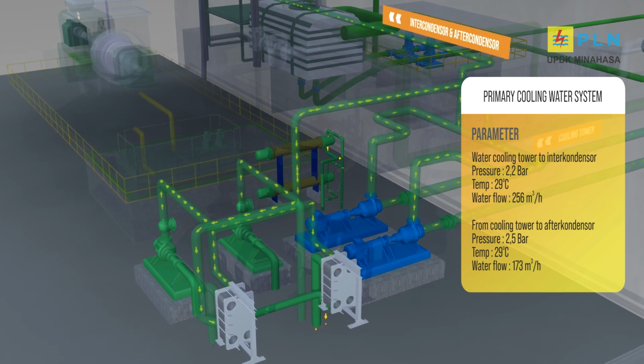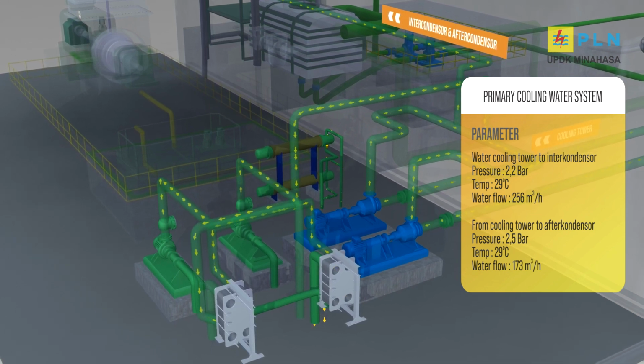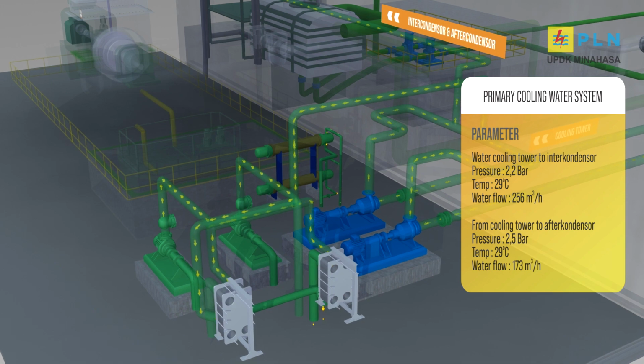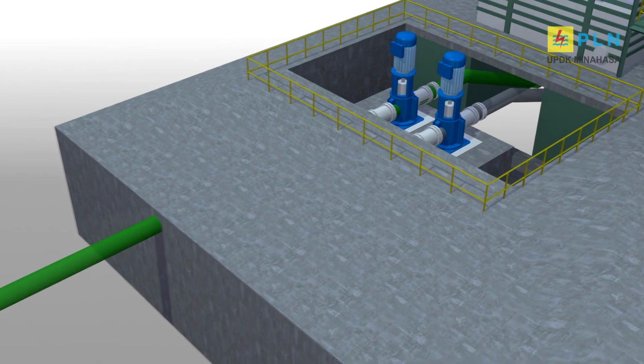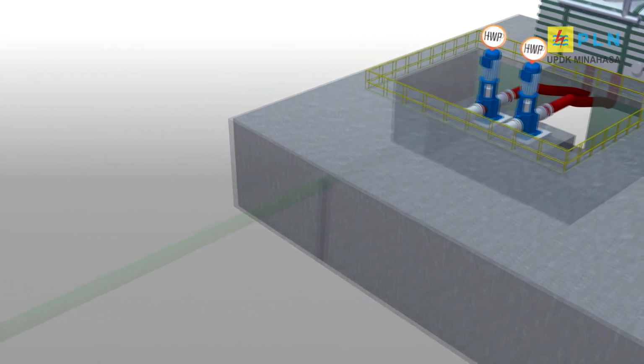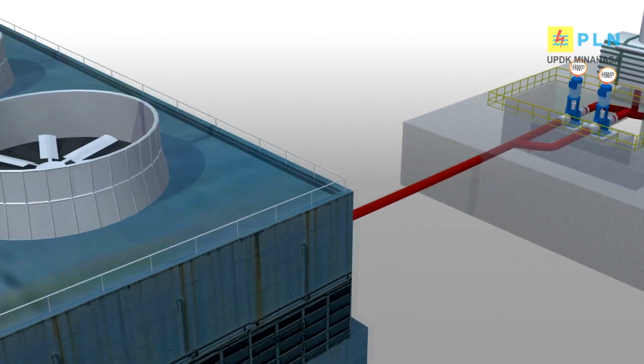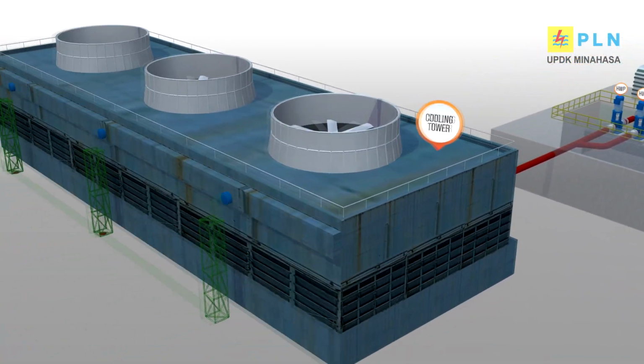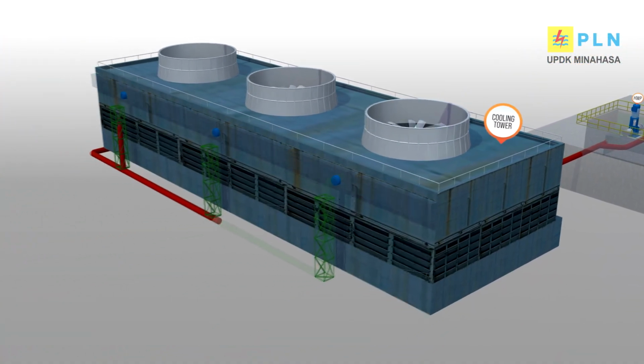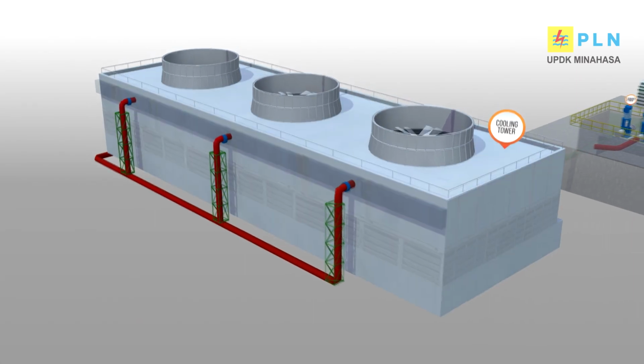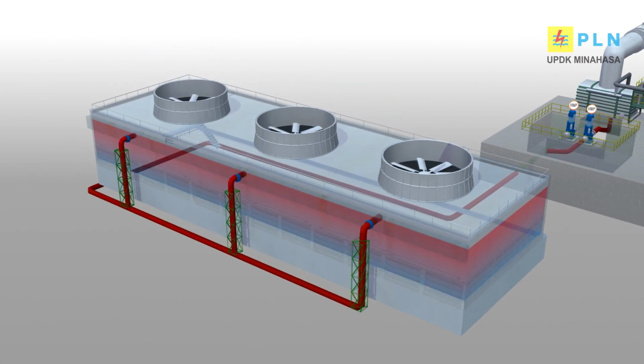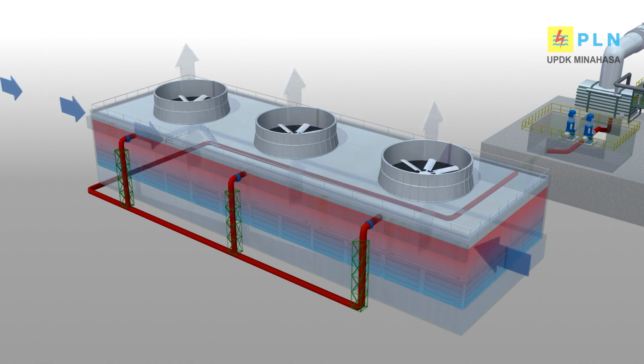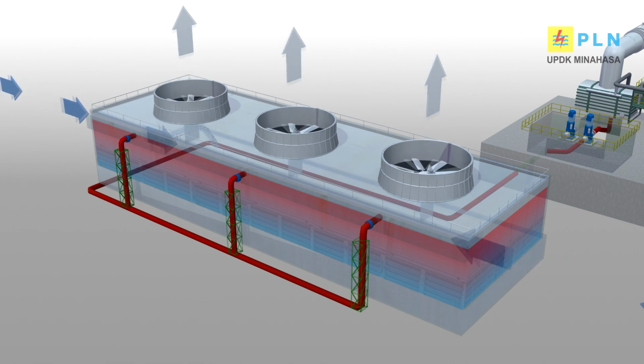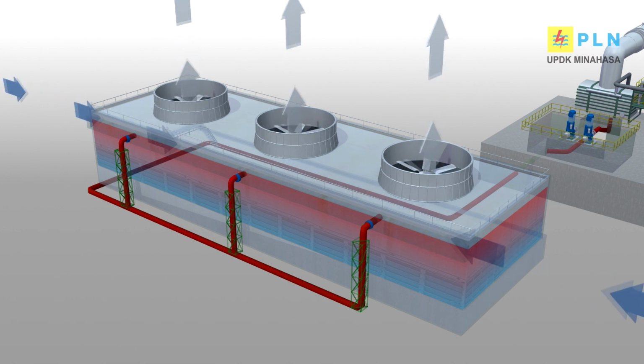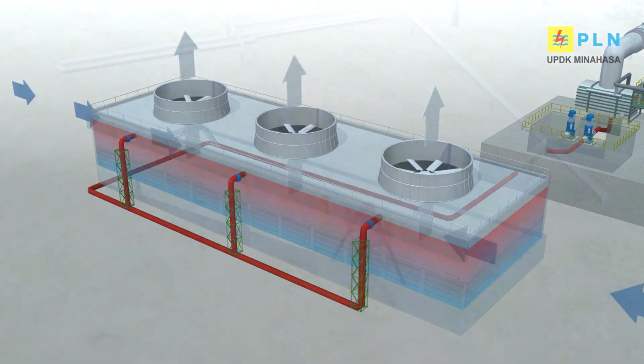The condensed water from condensation in the main condenser is then pumped using a hot well pump to the cooling tower. In the cooling tower, there is a process of heat exchange by convection between water and air with a counterflow, so that the resulting water temperature in the cooling tower basin is 28 degrees Celsius, to be recirculated to the cooling system.